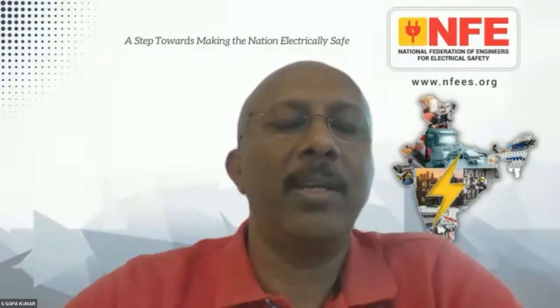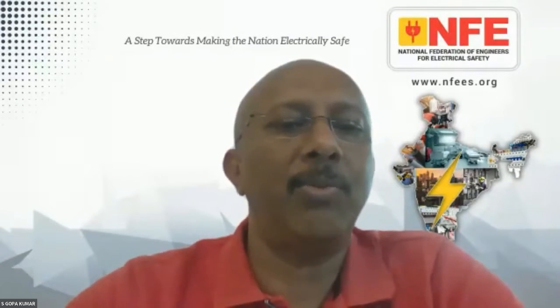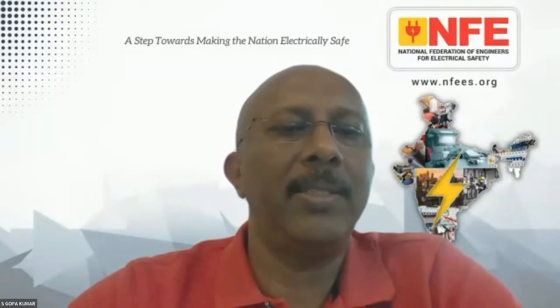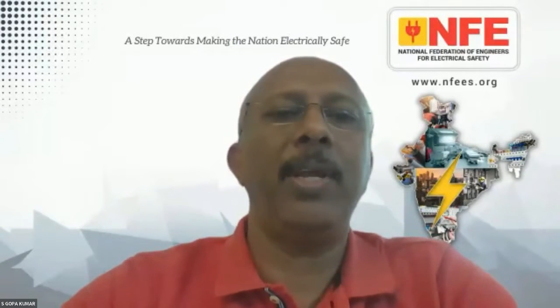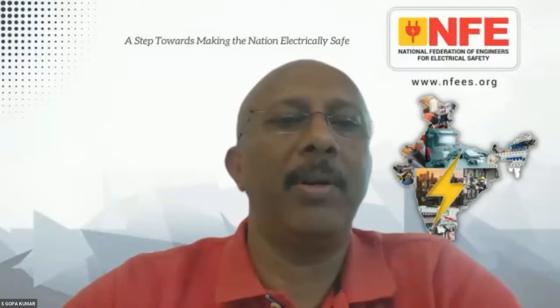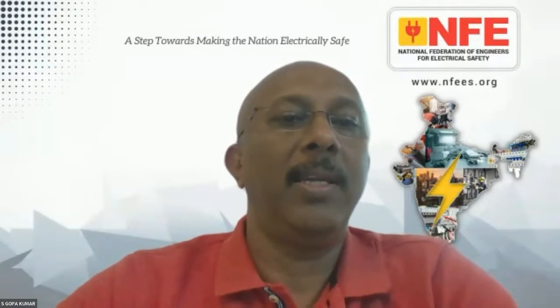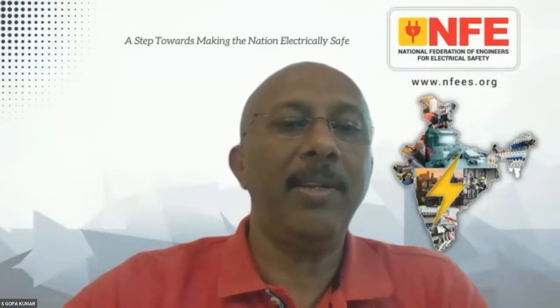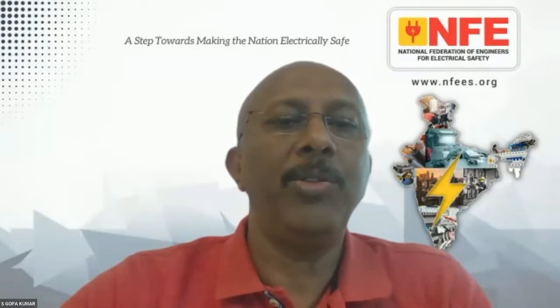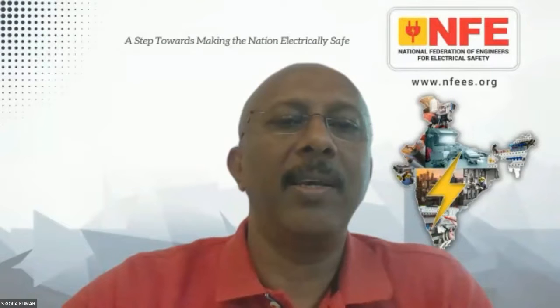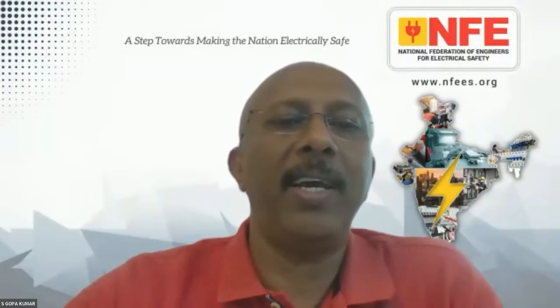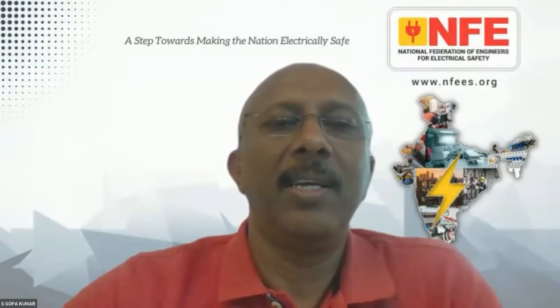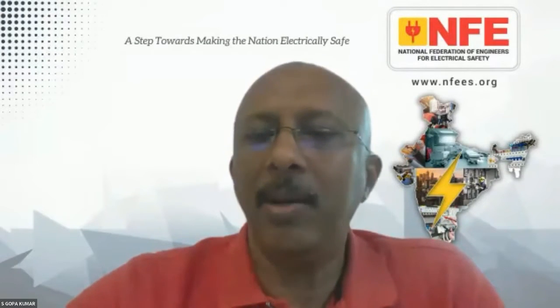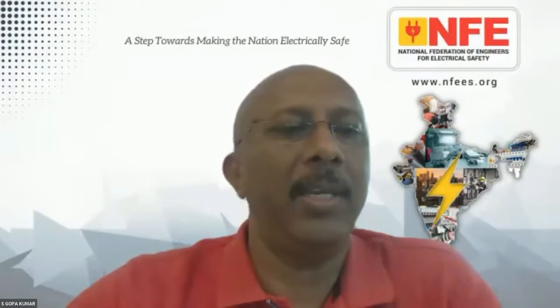Mr. Behra, please note that the regulation talks about the generator and transformer terminals as well as the body being connected to a common bus bar, with two separate connections. That is the requirement. Whereas your question was about earth electrodes and so on, which is not applicable. Actually, there are several questions, but none really related to the regulation. Somebody is asking about a requirement to prevent fire for solar installations. Has anybody seen a requirement included in the regulation about fire in solar PV?